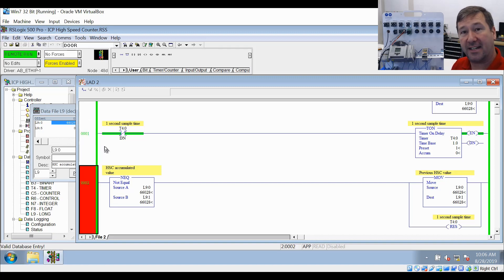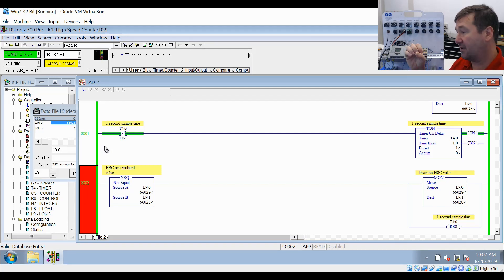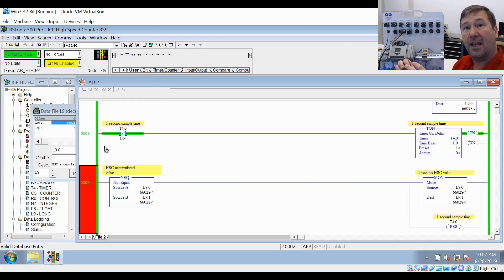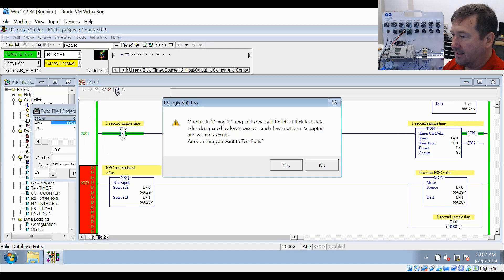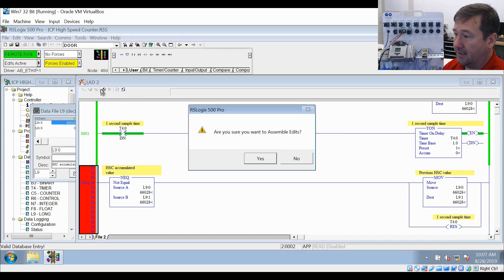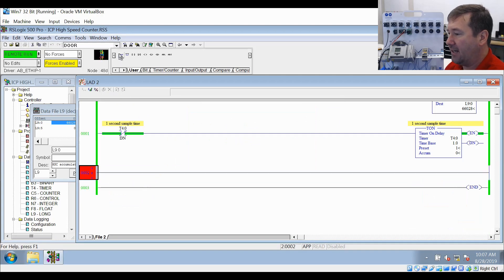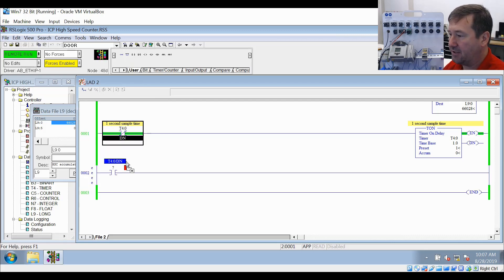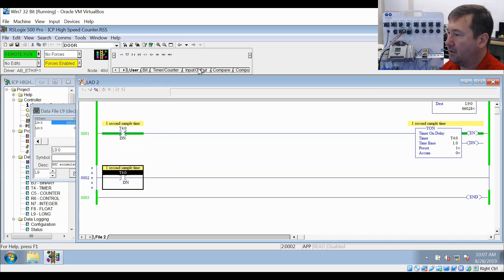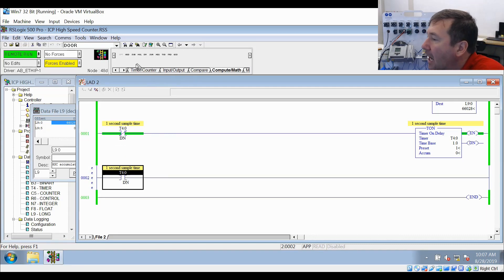Now that we have that one second sample rate set up, every time that done bit is true, we can subtract the current value of the high speed counter from the value from the previous time and come up with how much it's moved in the previous second. We're going to go ahead and delete this rung, test and assemble that, and then add another rung. We'll look at the same T4 colon zero dot DN and use an XIC instruction of it.